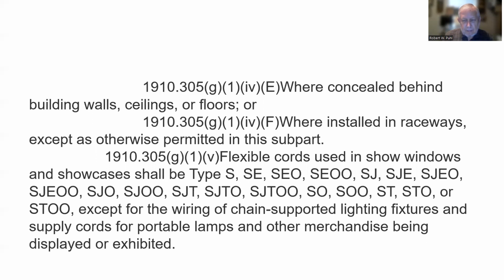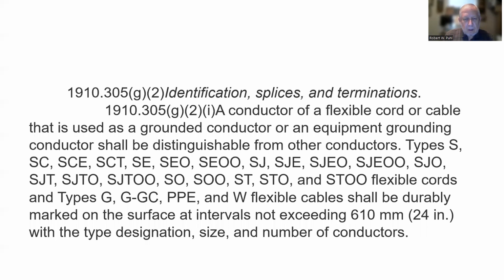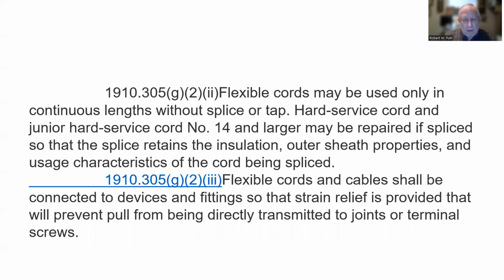And I'm not going to go over all these types of show windows for flexible cords. Identification, splices, and terminations. A conductor of a flexible cord or cable that is used as a grounded conductor or an equipment grounding conductor shall be distinguishable from other conductors. And there are the types of flexible cords. Flexible cords may be used only in continuous lengths without splice or tap. Hard service cord and junior hard service cord number 14 and larger may be repaired if spliced so that the splice retains the insulation, outer sheath properties, and usage characteristics of the cord being spliced.